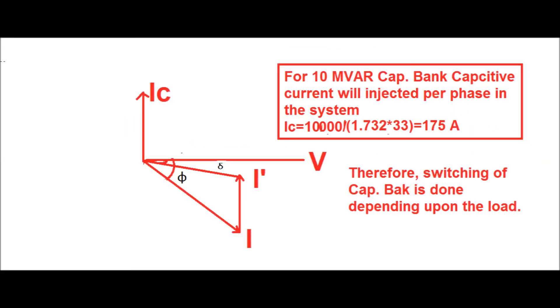How power factor is improved is shown in this vector diagram. Here, I is the lagging current which lags the voltage by power factor angle φ. After switching on the capacitor bank, the power factor angle is improved to δ and the current comes to I'. Since the capacitor bank capacity is 10 MVAR, the reactive power injected into the system will be 175 amperes per phase.